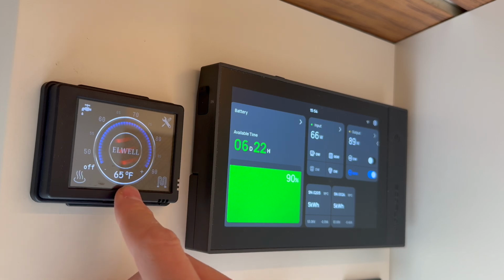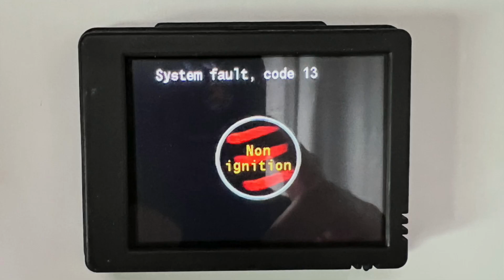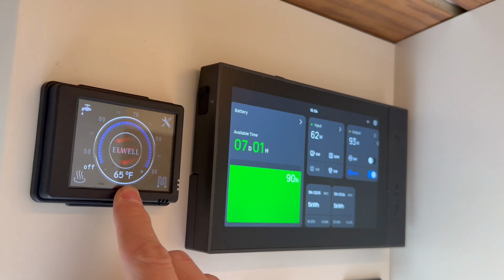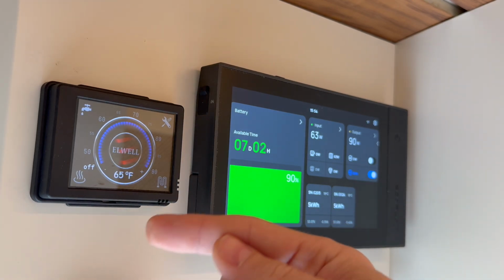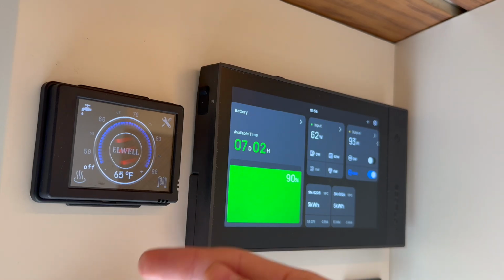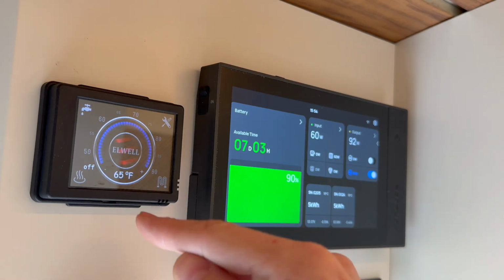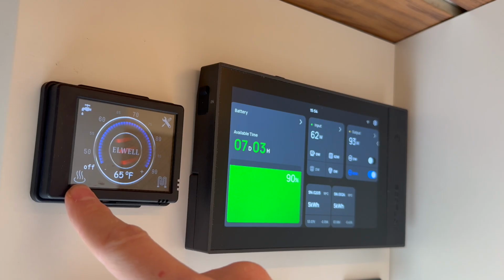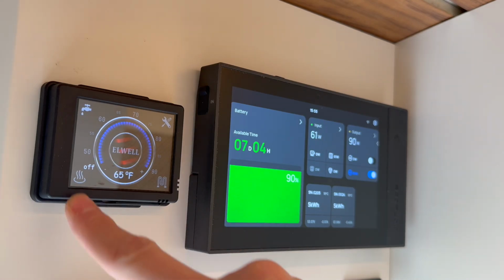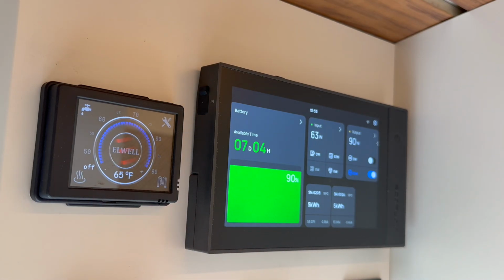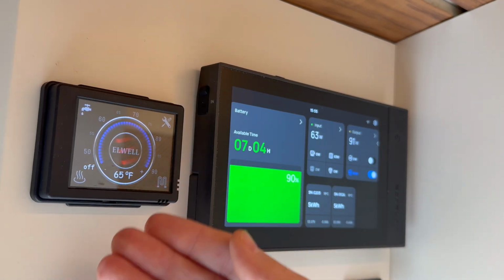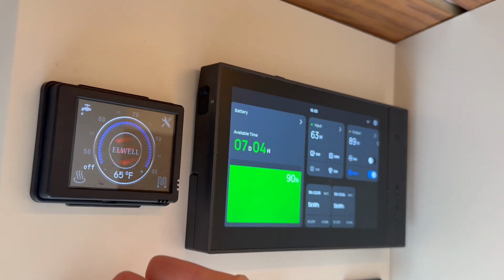If you get the error code ignition fail, well, exactly like flame break, most of the time it means that the fuel didn't get to the burner and that the ignition didn't start. It is the same thing. Start the heater up to 4 times if you need to make sure that the fuel gets to the burner and starts properly. Your burner was simply deprimed.